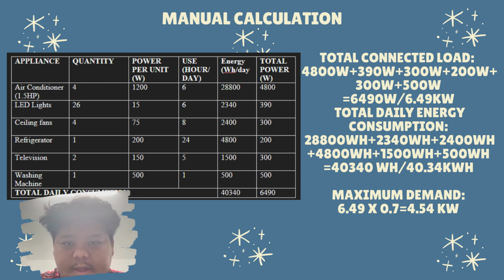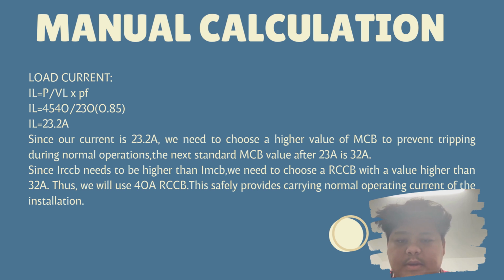For the total daily energy consumption, we will use 28,800 plus 2,340, 2,400, 4,800, 1,500 and 500. We will get 40,340 watt-hours or 40.34 kilowatt-hours. For maximum demand, we will use 6.49, which is the total connected load, times 0.7. To calculate the load current, we need to find IL by P over VL times PF.